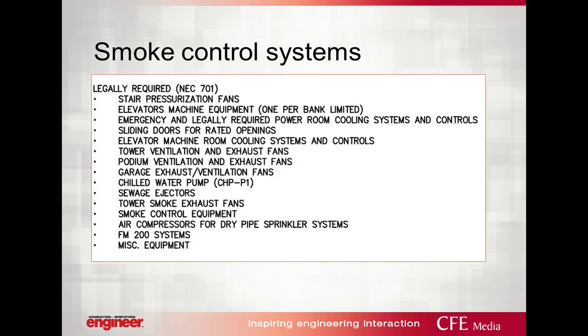And with regard to smoke control systems, this is just a clip out of what we utilize when we're doing design work in our facilities. It lists out legally required equipment for 701. Within that, you'll see items that are smoke control related, such as, believe it or not, sliding doors for rated openings, which could be deemed a smoke control item. Tower ventilation exhaust fans and sewage ejectors are not smoke control, but you need to take those under 701. Smoke control equipment, tower smoke exhaust fans, and stair pressurization fans are all utilized to make sure that the firemen can, typically, clean up the building and make sure that everybody's out.